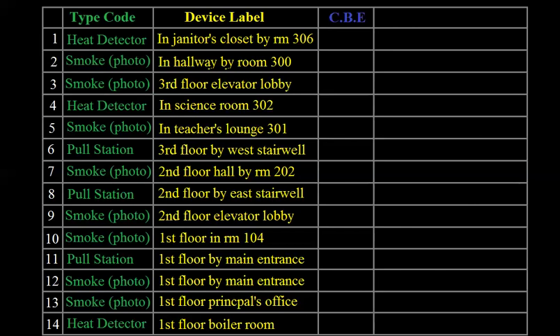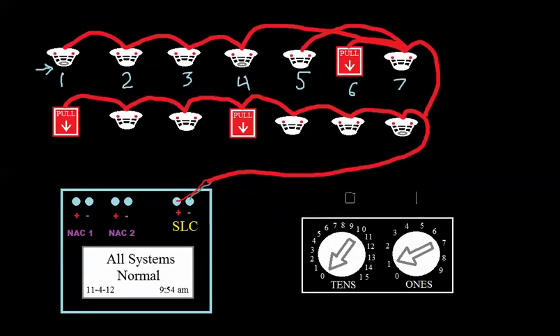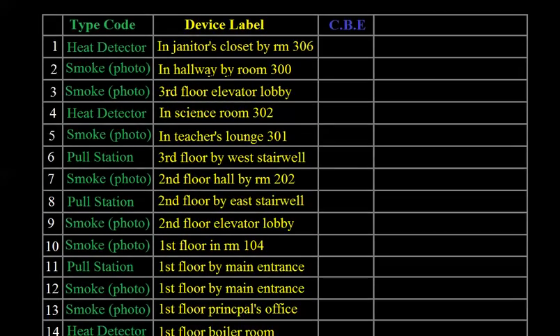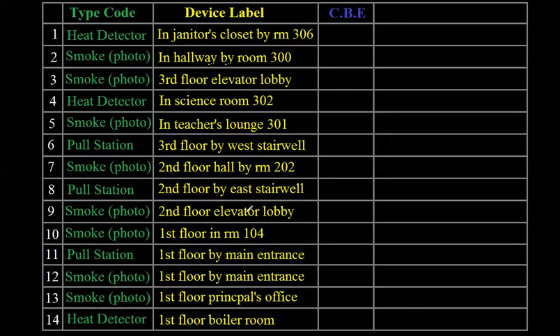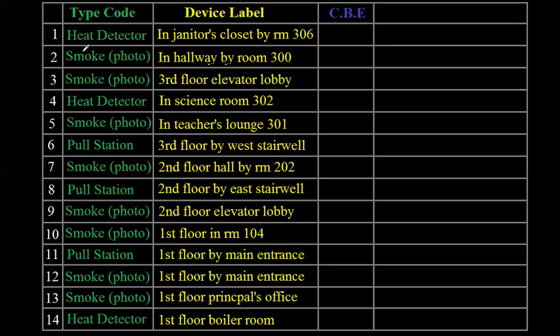If we scroll back up, we had our devices were one, two, three: heat detector, smoke detector, smoke detector. And you can see at the top here, I have number one is heat detector, then smoke detector, then smoke detector. Well, that column I labeled type code. Type code is something that we'll get more into in the future, but it's basically the way that you tell the panel what type of device is out there. And there's a lot of different options. Like I can have a smoke detector. The smoke photo is a common type code for the Notifier panels. But I could have a smoke detector that doesn't cause an alarm when it's activated. It causes a supervisory. So there's a different type code for that. I could have a fixed temp heat detector or a high temp heat detector, which would be like maybe 100, I forget what it is, 195 degrees or whatever. But anyway, that's basically what the panel really cares about. It cares about this device number.